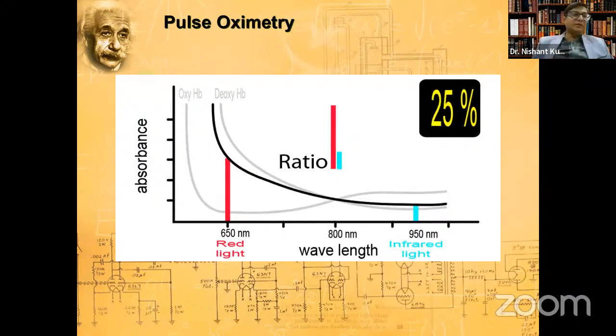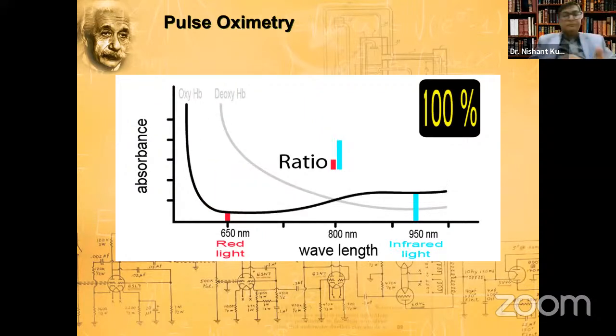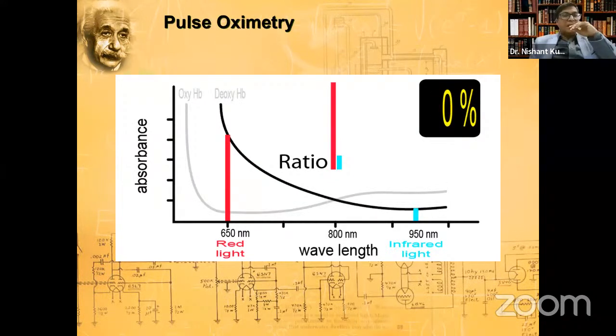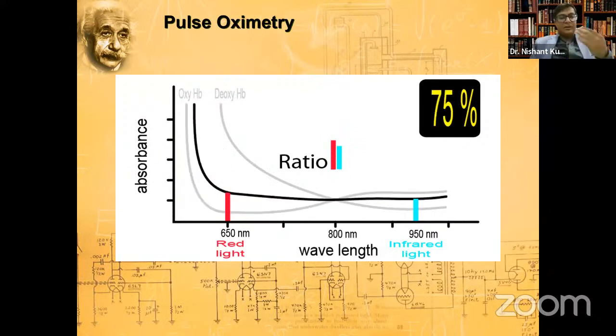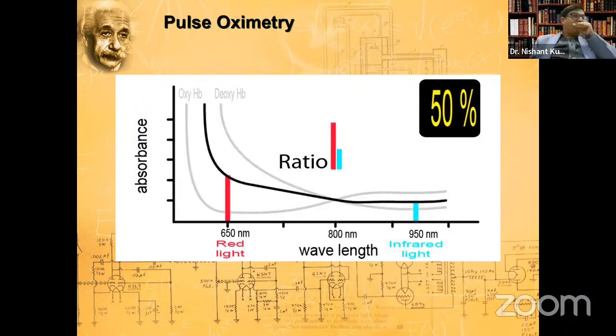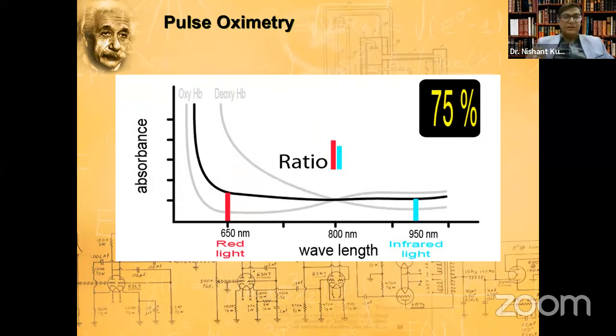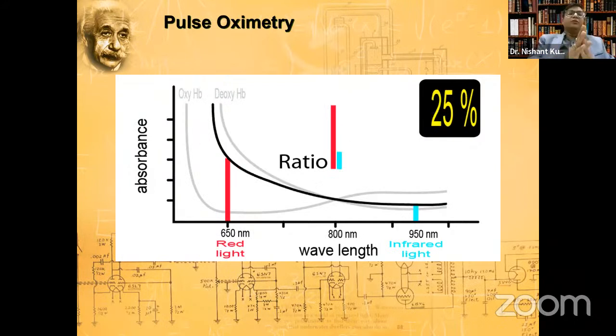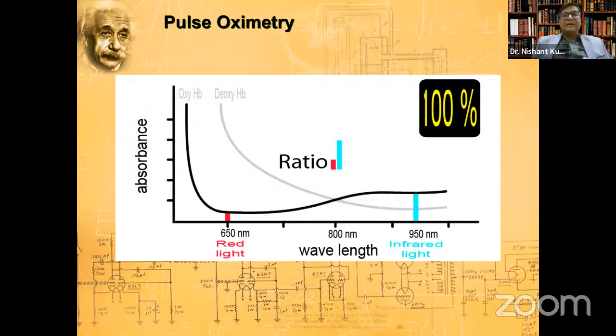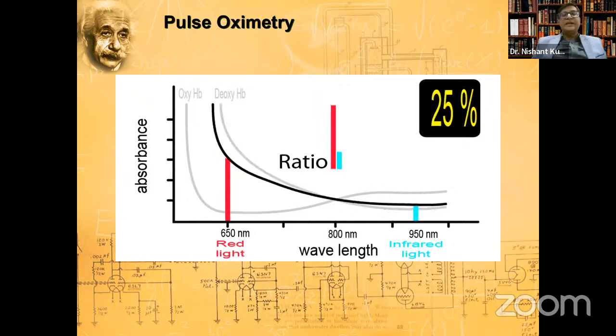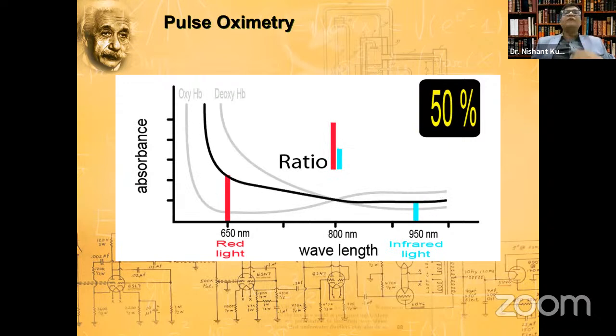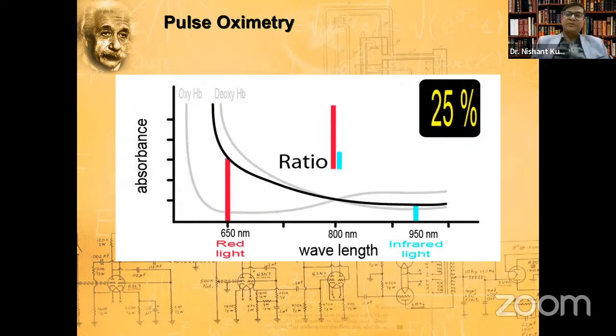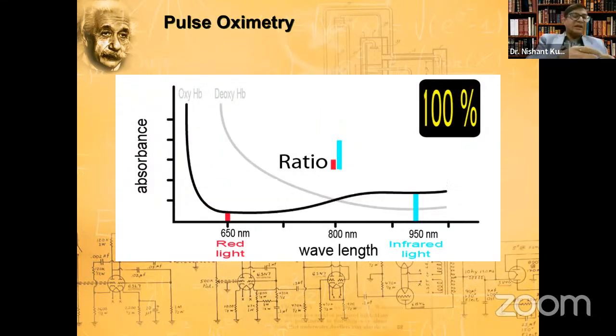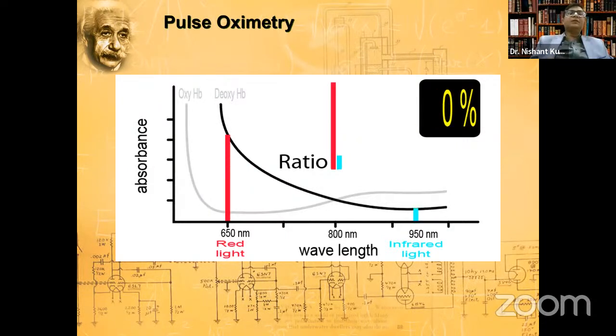So that is why we have confounding factors: a vasoconstricted patient, cold peripheries, and ambient light. When ambient light leaks through into the capillary, between the emitter and the detector, the ambient light will also contain some amount of red light and infrared light. As we know, white light is a combination of all the wavelengths, right? That is one of the Newtonian principles. So when there is interference, or a bright light at the detector, some unmeasured amount of red and infrared light will be detected by the pulse oximeter, which was not there initially. That is why you might get wrong readings if the ambient light is too much. So the best thing is to protect it from ambient light. That is why we say that if the probe is not covering the finger properly and there's a bright light outside, the pulse oximeter readings might be wrong.